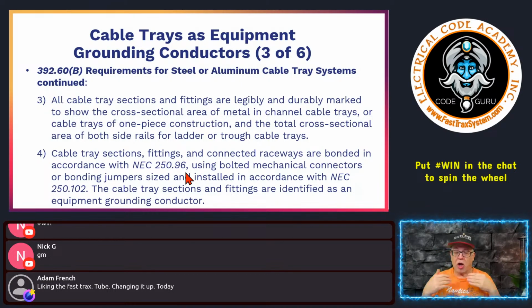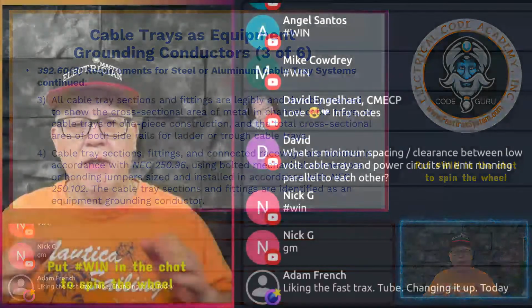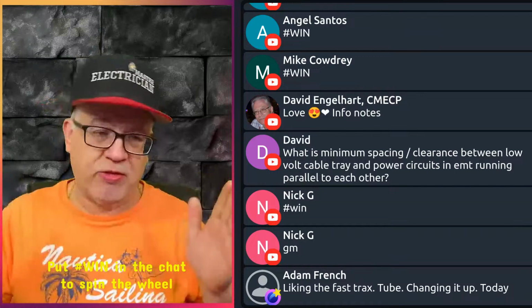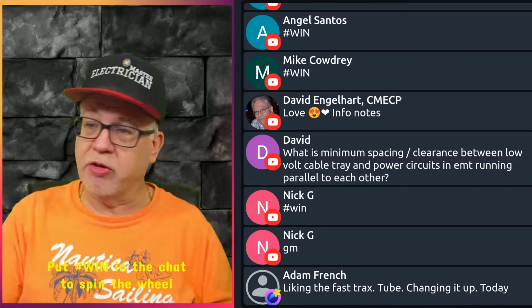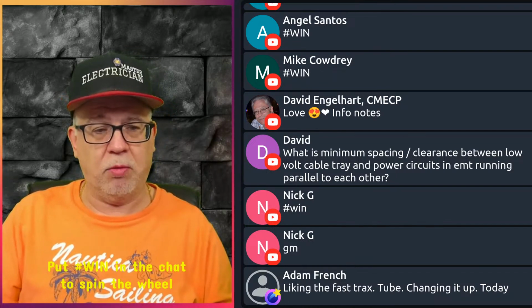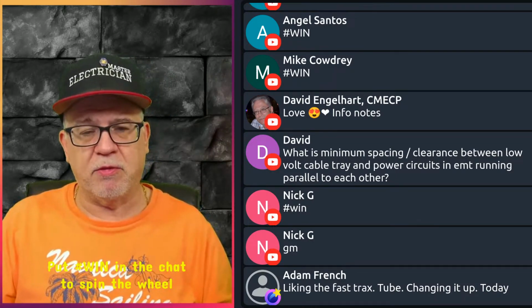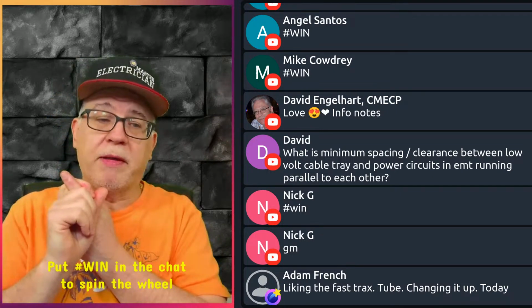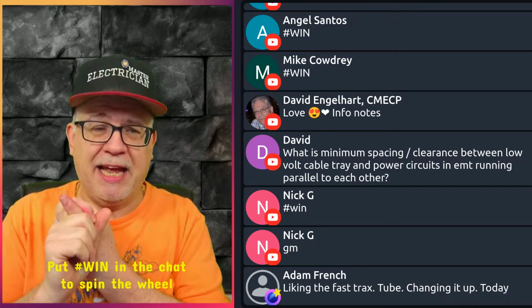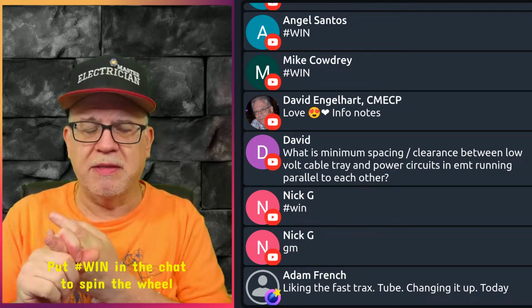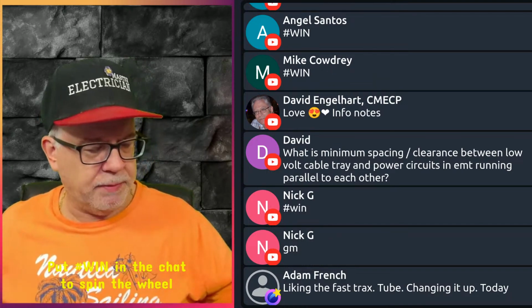And so you're going to obviously base this on the worst case scenario, or the largest conductor in that tray. That's what 250.102 is based on, the size of the conductors, okay? Making sure, no different than we normally do for grounding and bonding, that it acts as one. We don't want any weak link in there anywhere. An undersized jumper would affect the ability of that piece of equipment to carry a low impedance effective ground fault current path. It would create a weak link somewhere in the system and nullify its effectiveness. We don't want that, okay?